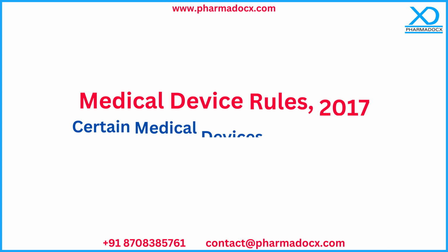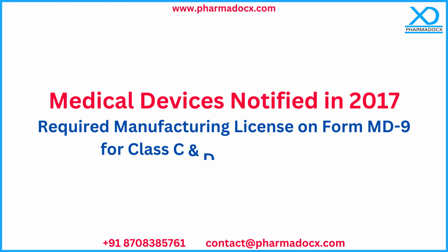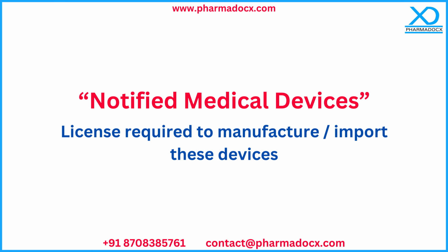When the medical device rules were first introduced in the year 2017, there were certain medical devices which had been notified. The medical devices which had been notified in 2017 required a manufacturing license on Form MD9 for Class C and Class D medical devices effective immediately. These devices were known as notified medical devices, meaning a license was required for either importing or manufacturing them.